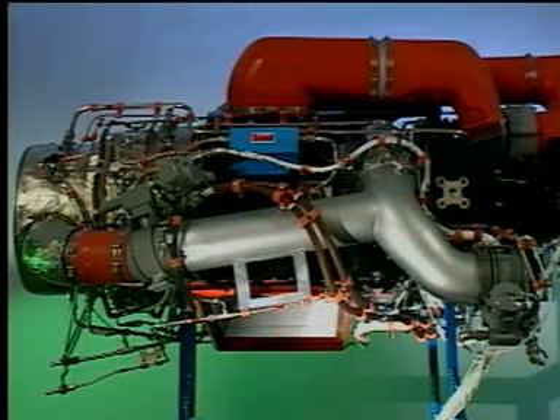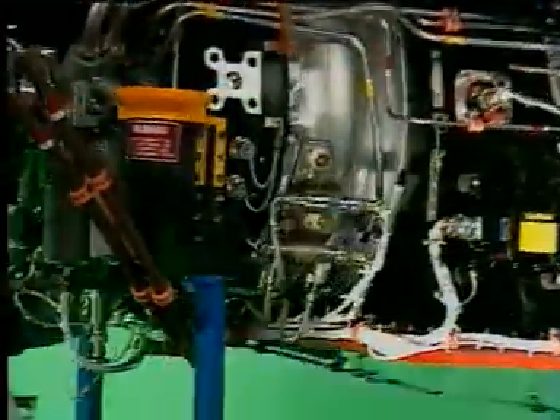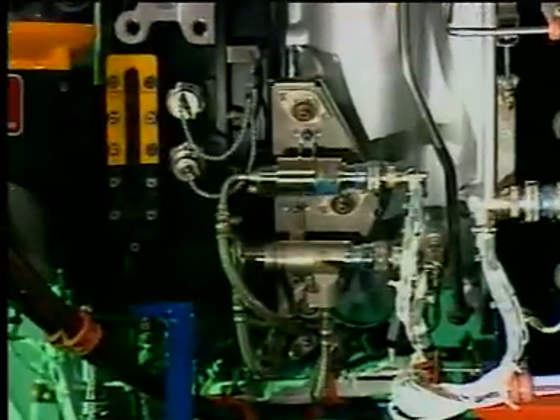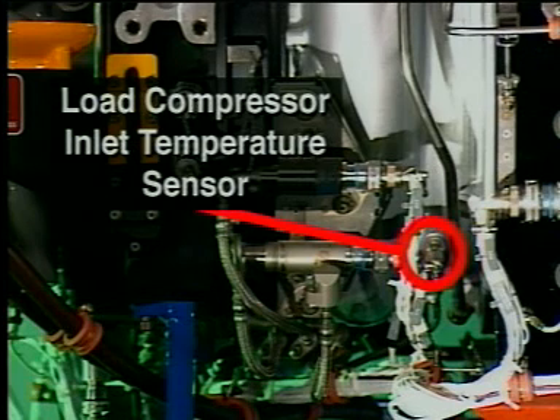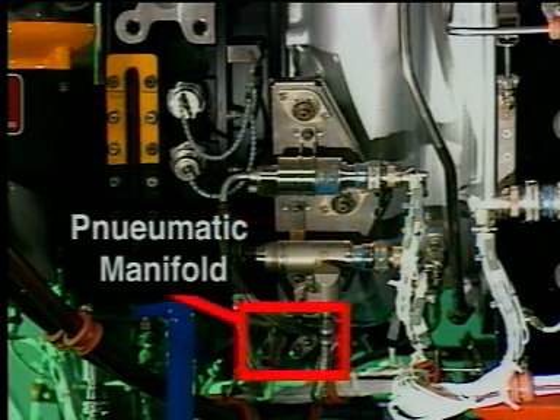The load compressor inlet and outlet temperature and pressure is monitored by the electronic control box. The load compressor inlet temperature sensor is installed at the 7 o'clock position on the load compressor housing. The data is used for fuel flow scheduling, over temperature shutdowns, and reverse airflow detection.